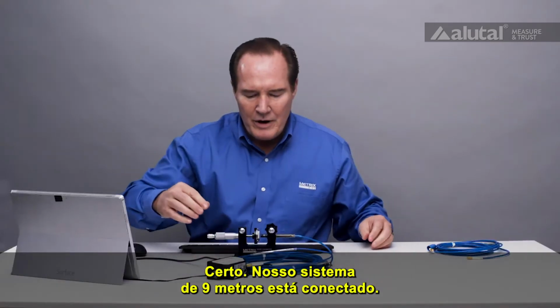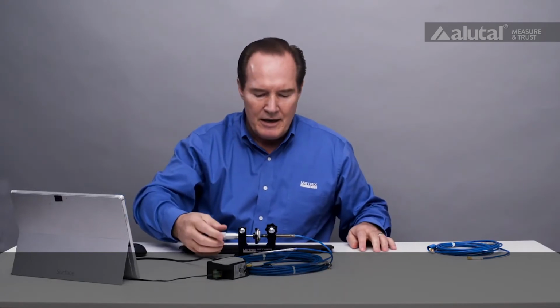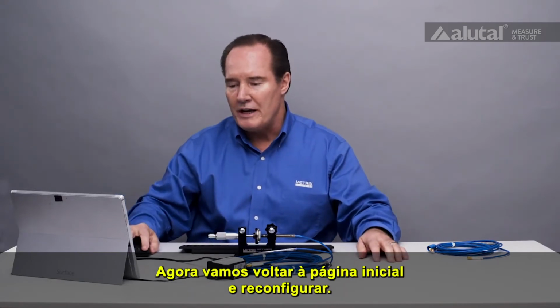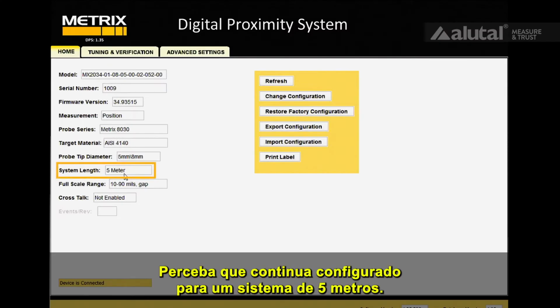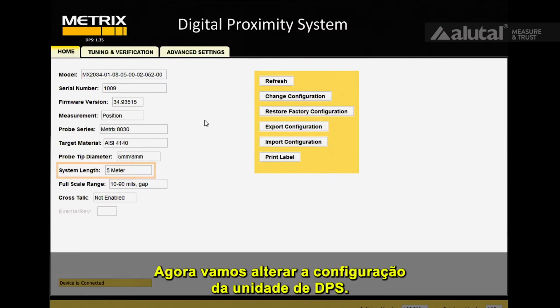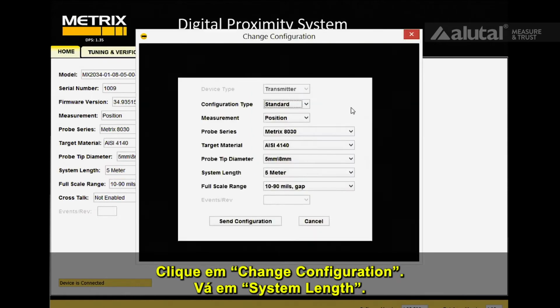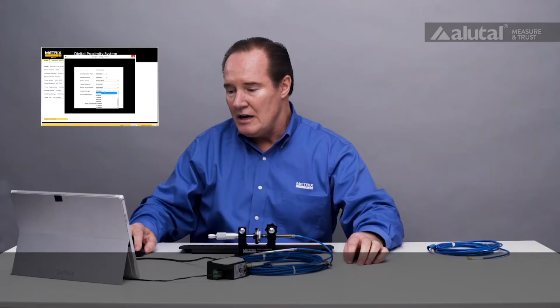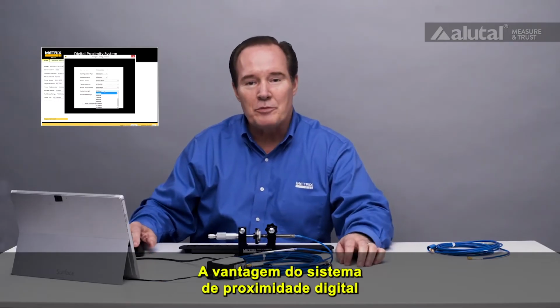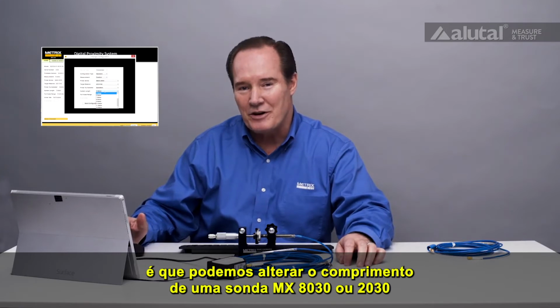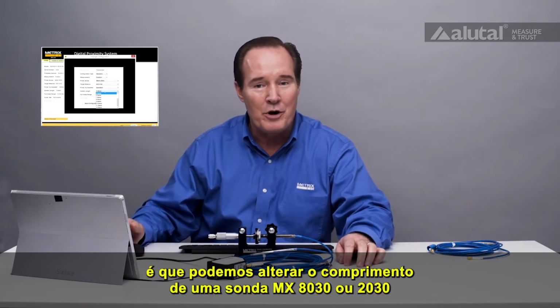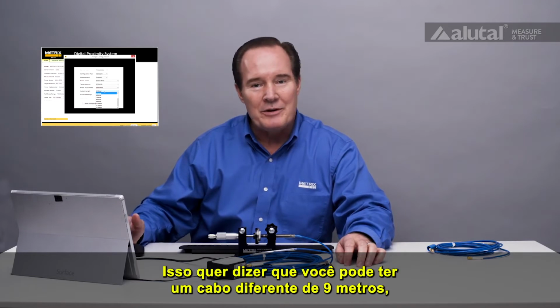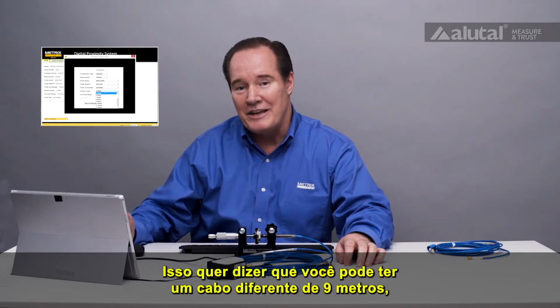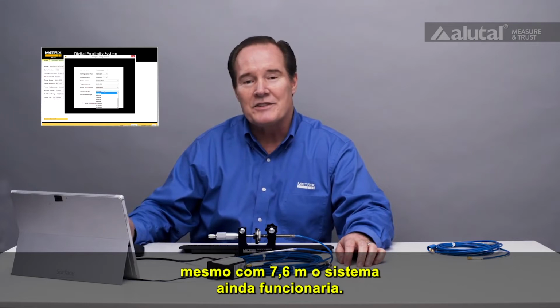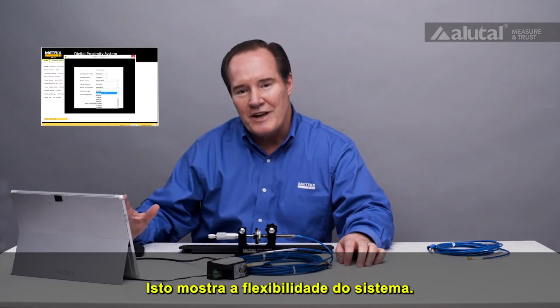All right, we have our 9-meter system connected, and what we'll do is we'll go back to the home page and we'll do a reconfiguration. So we can see it's still set up for a 5-meter system. What we're going to do is we're going to change the configuration of the DPS unit. So we'll change the configuration, go down to system length here, and what's nice about the digital proximity system, we can actually change lengths for an MX8030 or MX2030 probe in 1-meter increments. What that means is you could have a cable length other than 9, you could have like 7.6, and the system would still work. So this shows you the flexibility of the system.